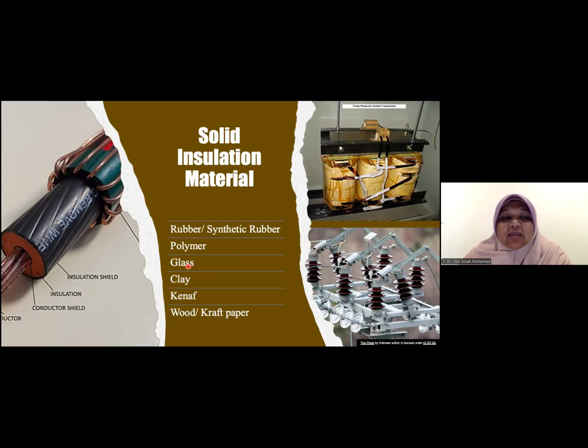So we have glass, also insulation. We have clay. This one is made from clay. This is glass, the white one. This one is a glass insulator. This one is the clay insulator. This is a conducting wire, so it is insulated from the live wire to the tower. Here is the transformer. So we have Kraft paper, here is the Kraft paper. It insulates between the windings in the transformer. And we also have wood and Kraft paper at the equipment.